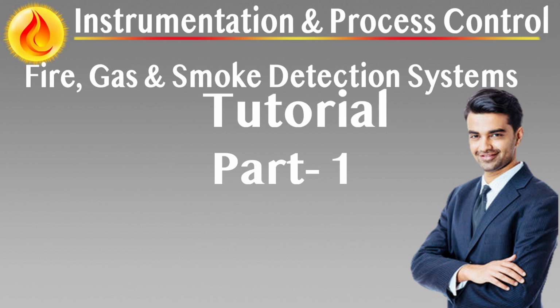Installation best practices. Avoid locations with heavy vibration or frequent optical obstruction. Use only in clean, dry air environments. Do not install where mist or condensation may form on the optics. Always ensure the sensor head is aligned and accessible for testing and diagnostics.